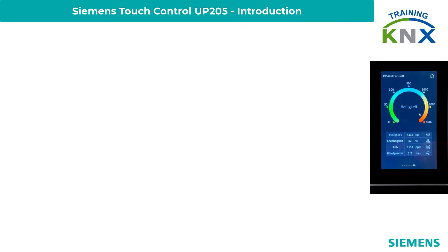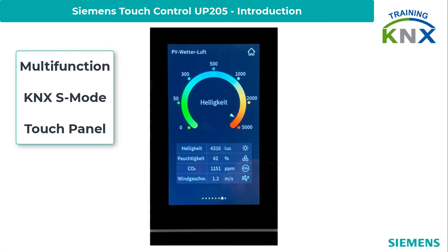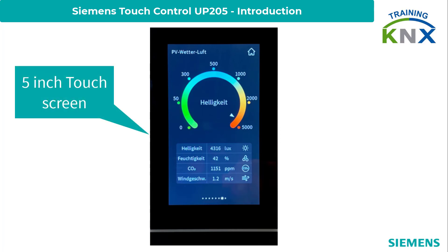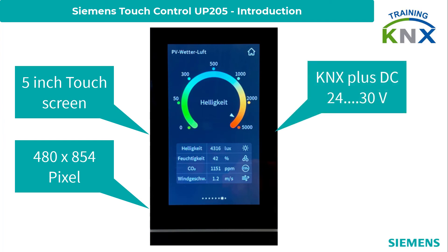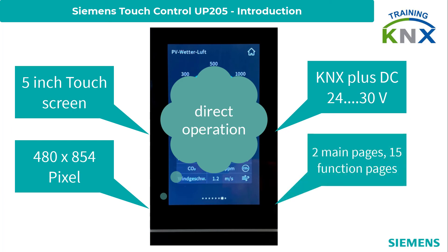The Touch Control TC5, referred to as TC5 in the following, is a multifunction KNX S-Mode touch panel for display, operation, and control. The device has a capacitive color touch screen of 5 inches with a resolution of 480 by 854 pixels. It is supplied via KNX together with an auxiliary voltage of 24 to 30 volt DC, and is operated directly via the touch screen.